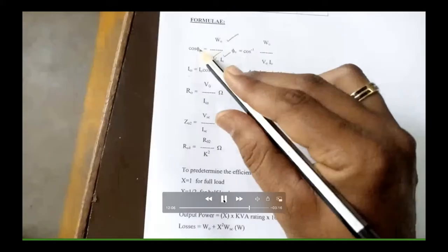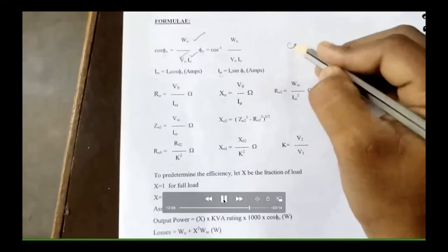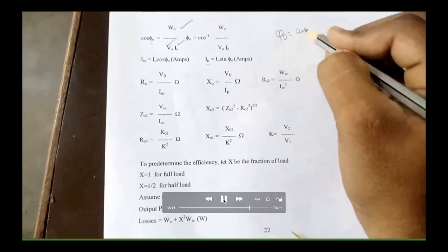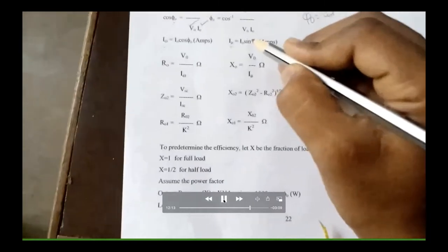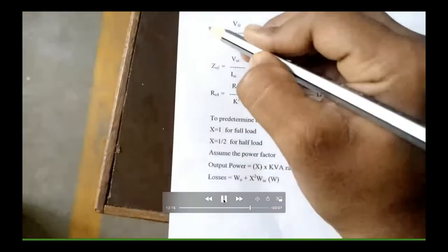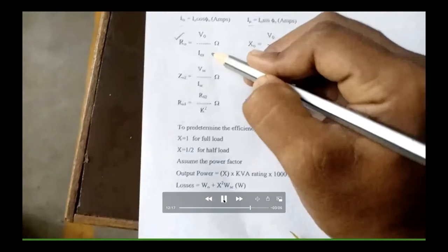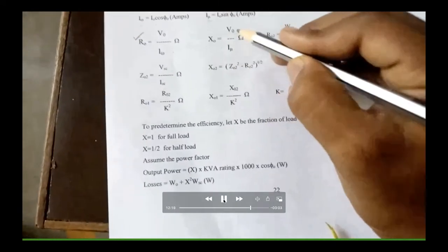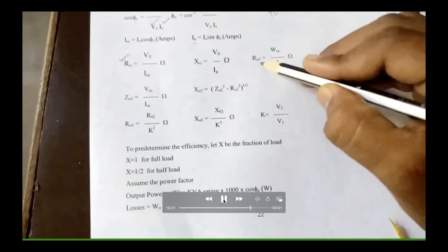So take reciprocal of cos phi. So phi is equal to cos inverse of that value. Then you can take sin phi naught. Then R naught will be V naught by IW, and X naught reactance will be V naught by I mu, and R02 will be WSC by ISC square. VSC is from the short circuit power. You can calculate it.